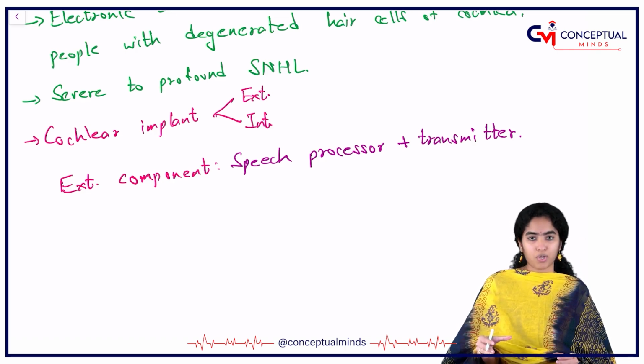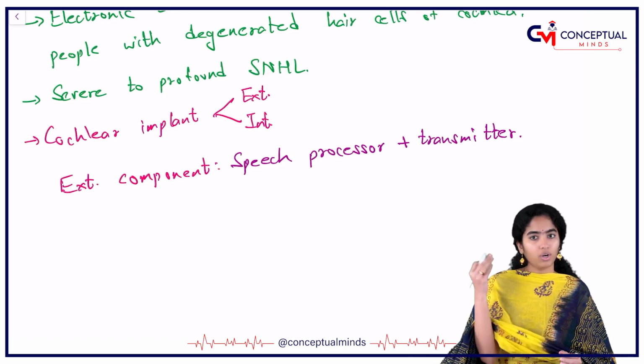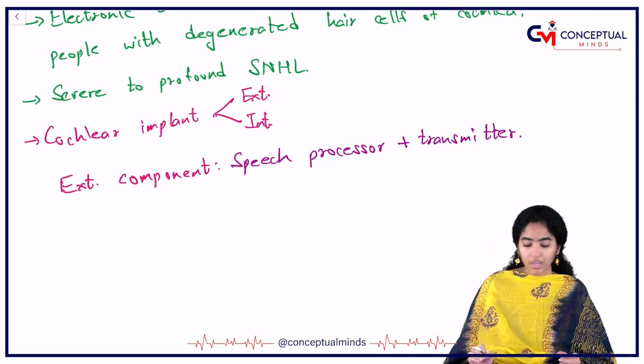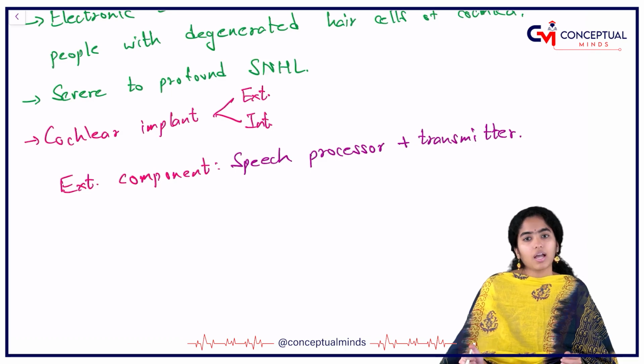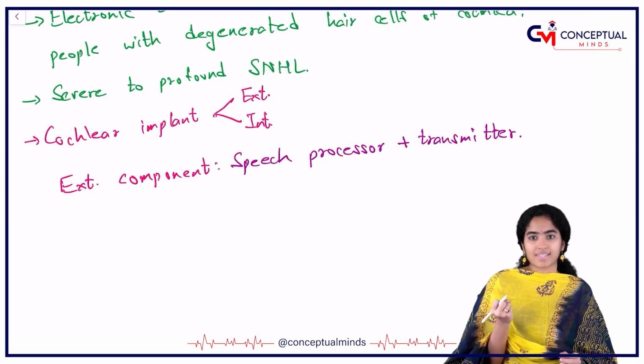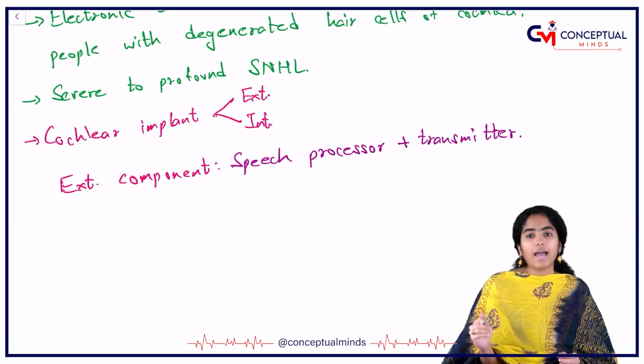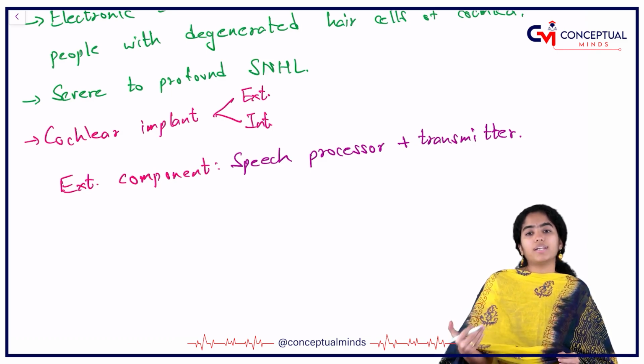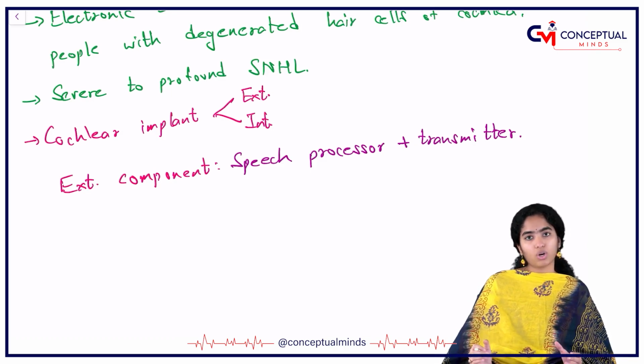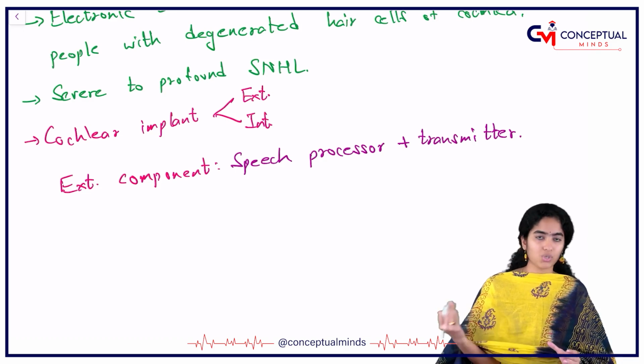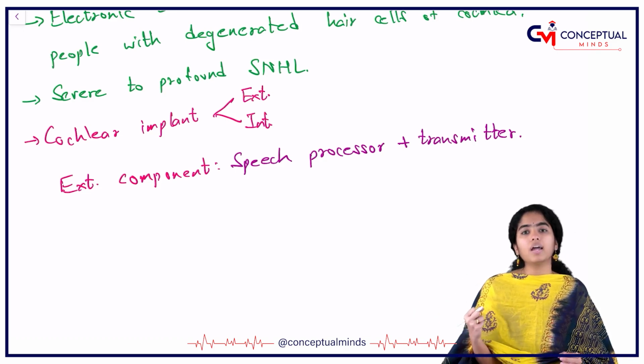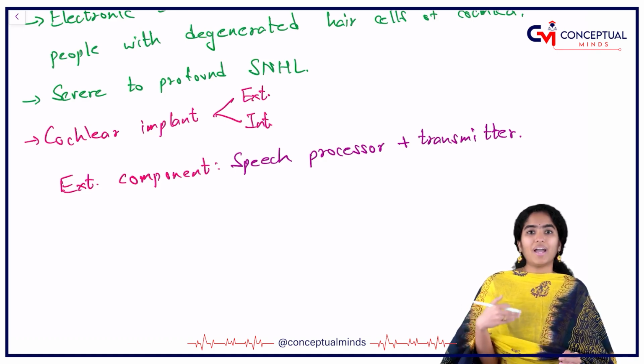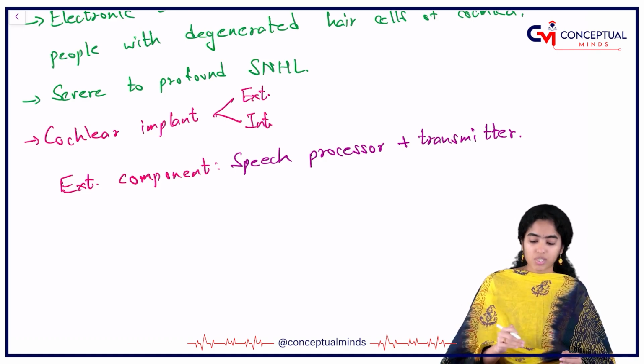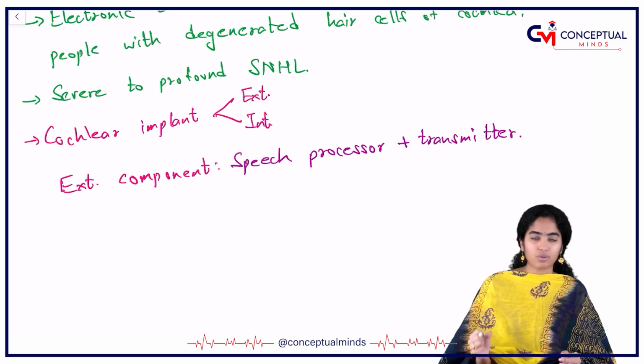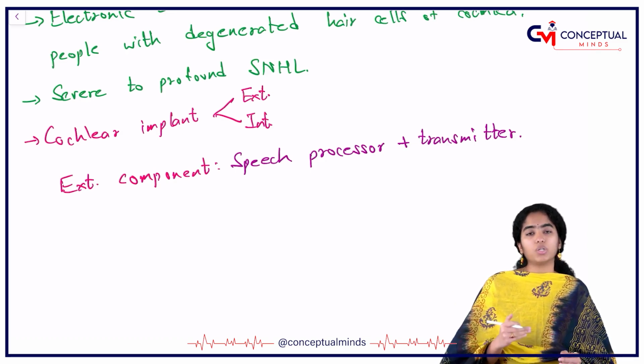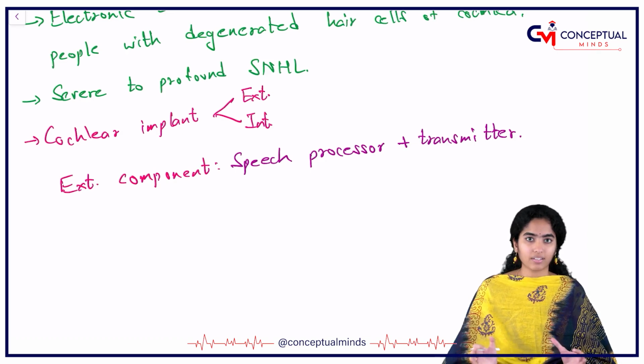Now this speech processor is worn either on the body or you can keep it behind the ear. Behind the ear is usually preferred. And this will capture sounds from the external environment and it converts it into digital signals. Now why am I not calling it a microphone? Because microphone also captures sound from external environment, but a microphone converts it into electrical signals, whereas the speech processor collects sounds from external environment and converts it into digital signals. Is that clear to you?